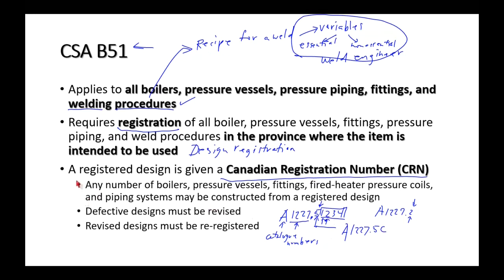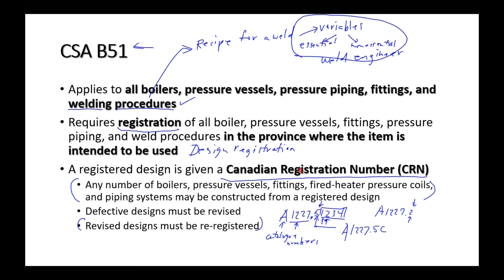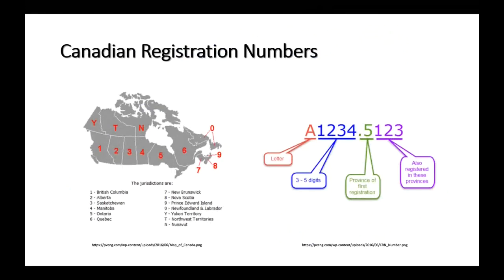Once you have a CRN, you can build any number of those boilers, pressure vessels, or fittings to that design — build a million a day if you want. You're registering the boiler design, not every individual boiler. If the manufacturer alters the design, that requires a new CRN. That's CSA B51 in a nutshell.